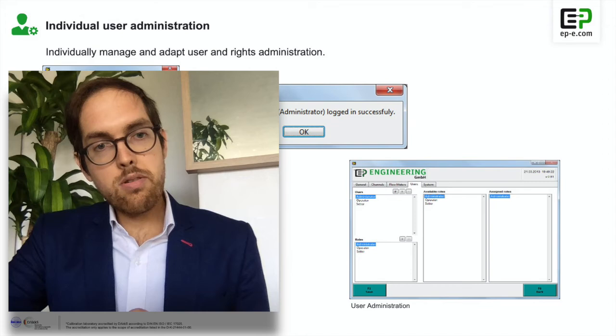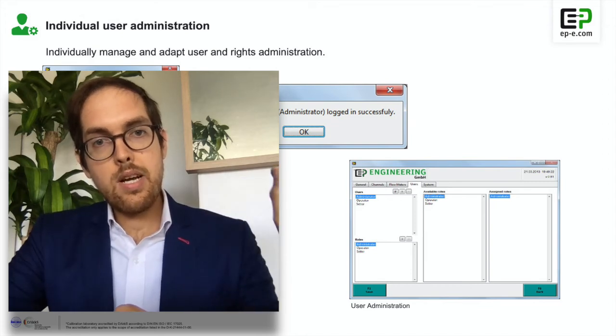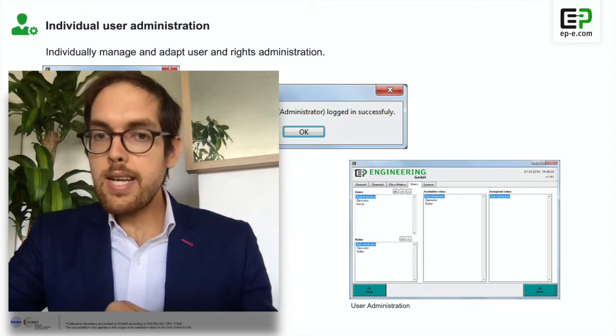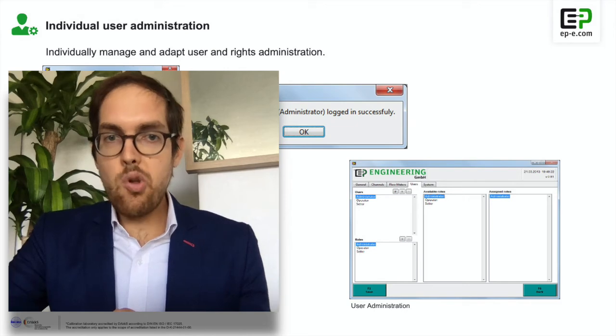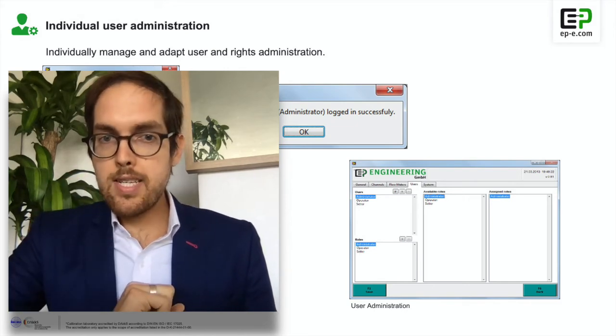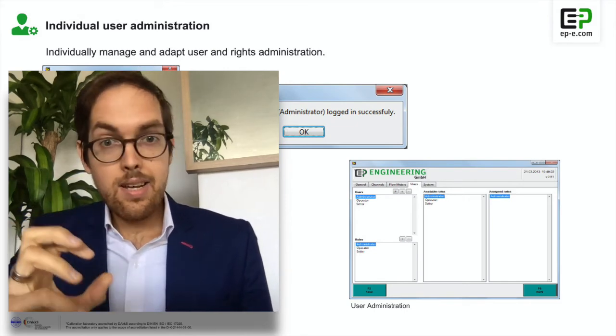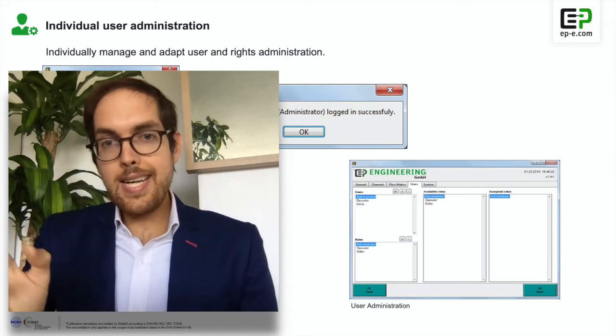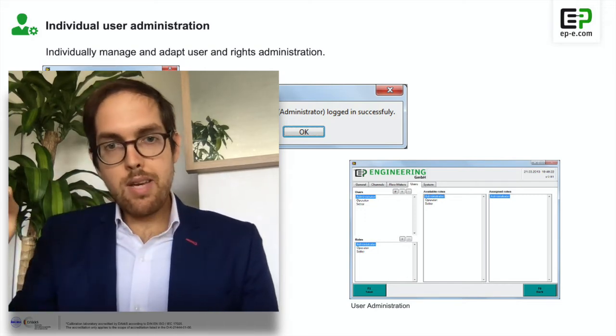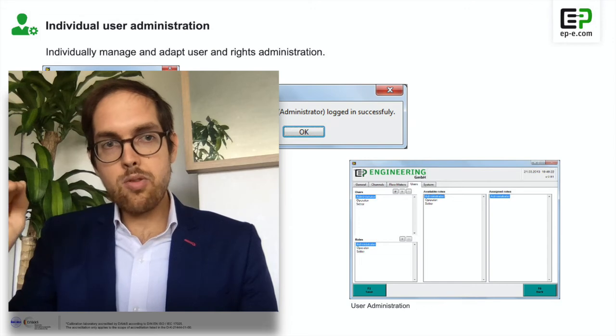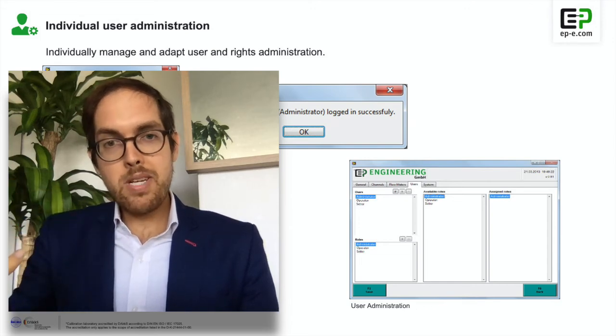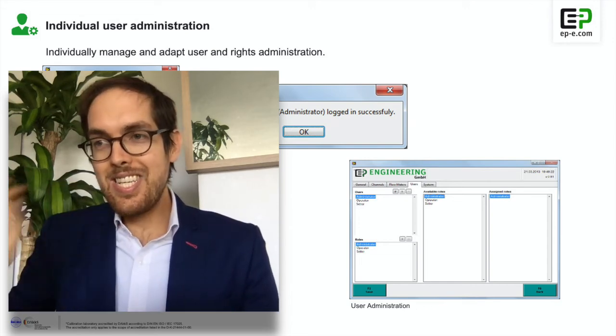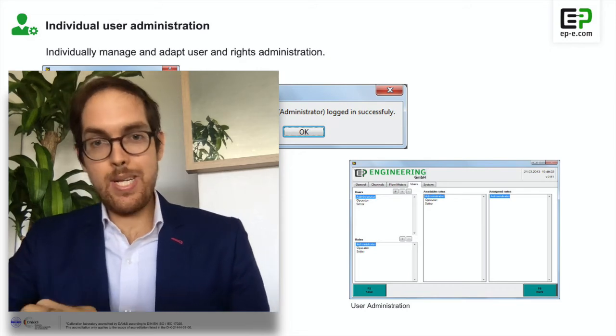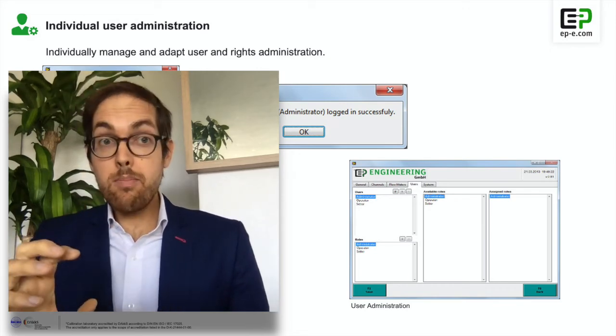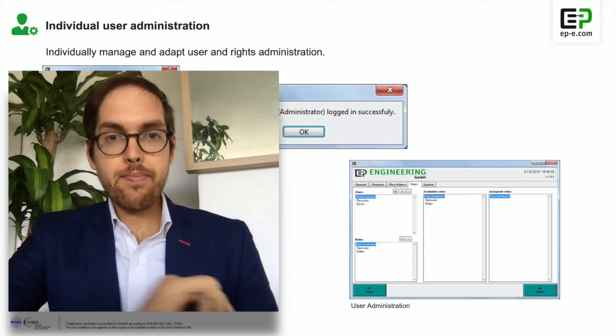This special user can have only the allowance to change calibration data, but not adjustment of test plans. Because again, if someone is changing a test plan, the machine will give you a green light, everything is good, but because the parameters are changed, it is actually not as you want it to be when it's good. Therefore the user management is really important.